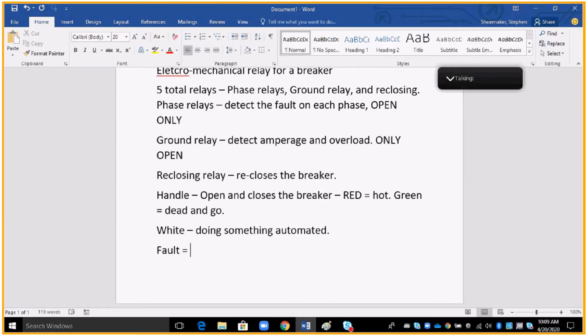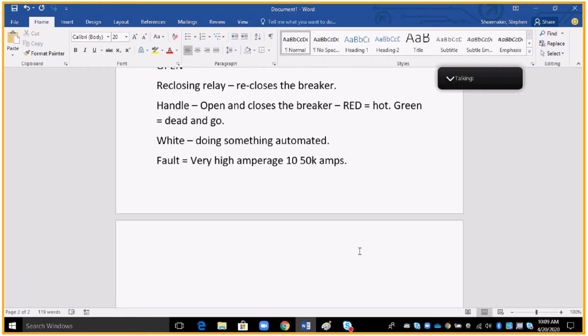The attributes of the fault itself concerning the breaker, it's very high amperage. Sometimes between 10 to 50,000 amps. This is extreme. When we have a fault on our phase out there and the relay recognizes that fault to be in this situation, it's going to send an open signal to remember, phase relays only open the breaker. I think I hit one too many. Nope. Overload.